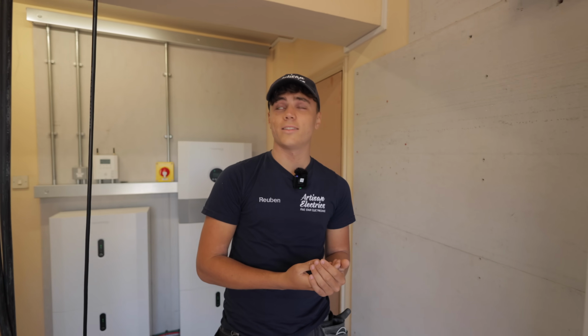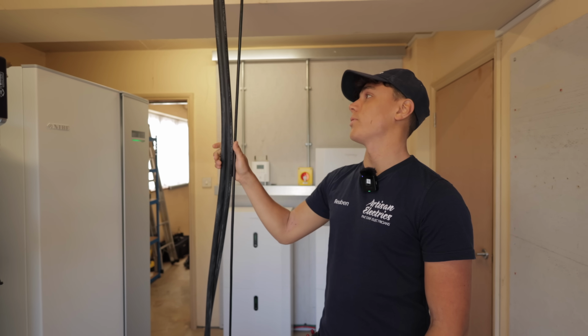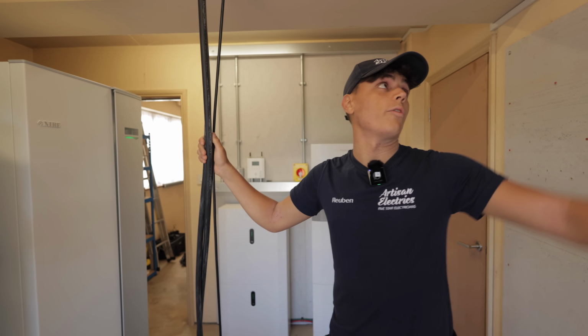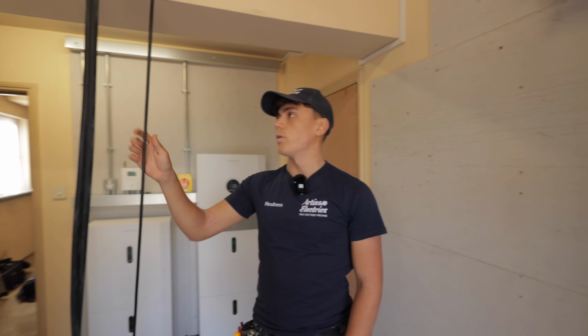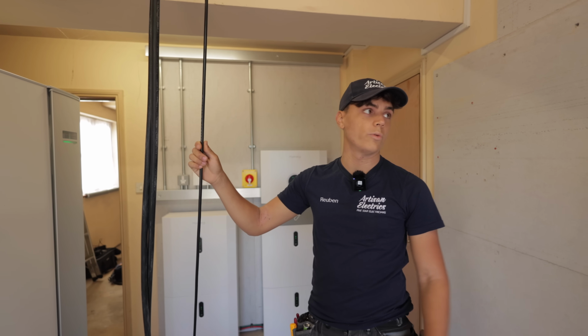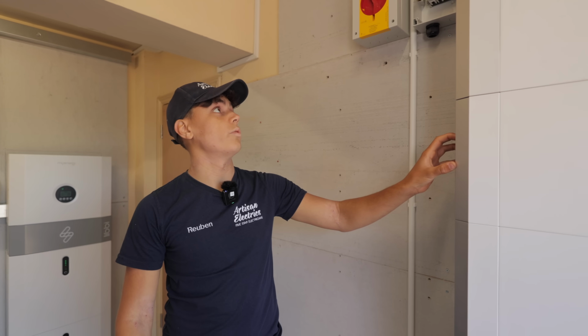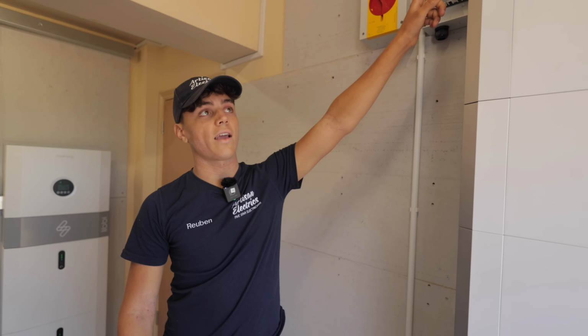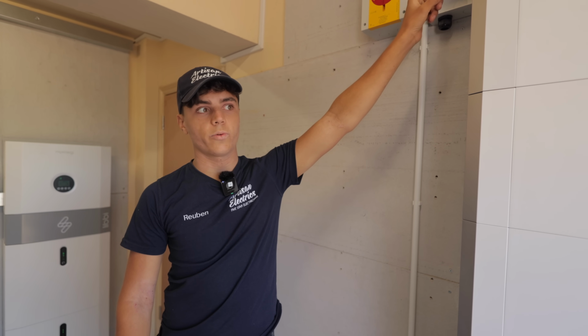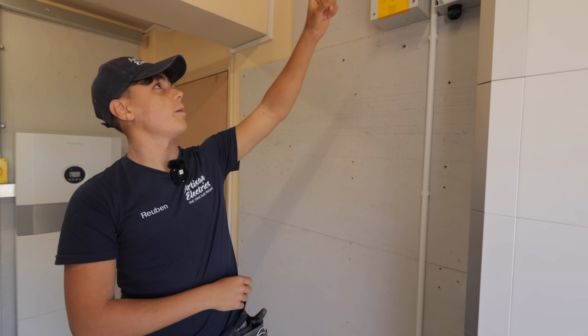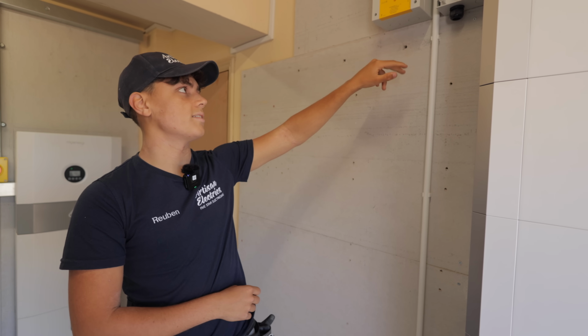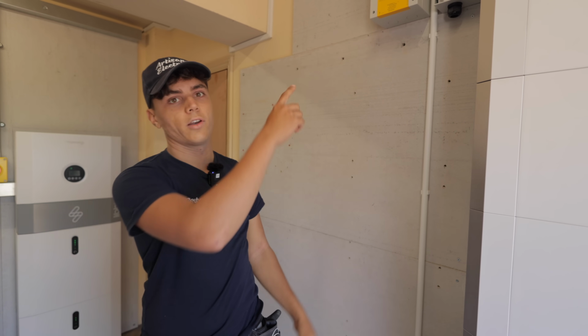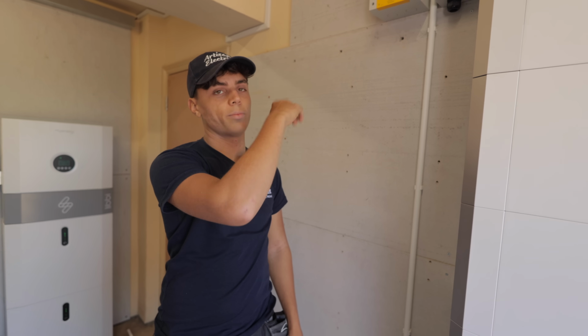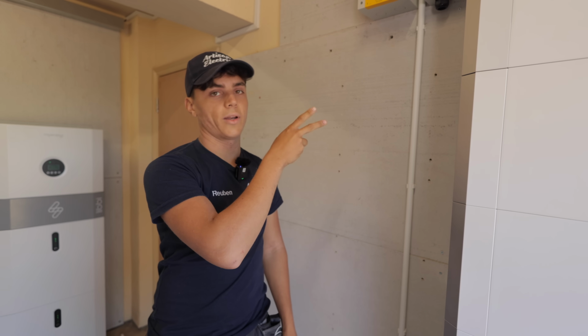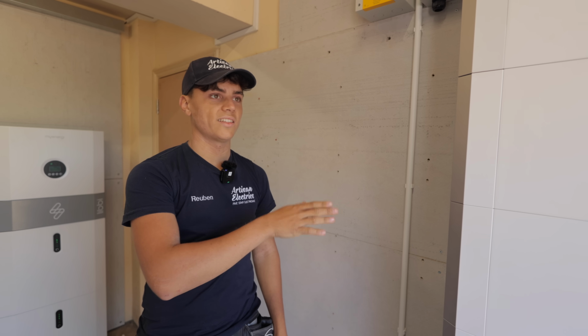Day 2. We've got these cables from yesterday, two of the armoured cables running to these two isolators, an armoured Cat 5 going to the battery we installed, alongside another Cat 5 we just ran from a network switch. It shouldn't be too bad really. I just need to drill a couple of holes in the ceiling, drop them down into the isolators, leave a bit of a loop in the ceiling for some slack if these ever get moved, terminate it on the gateway side, and test it all. Shouldn't be too bad, I don't think.